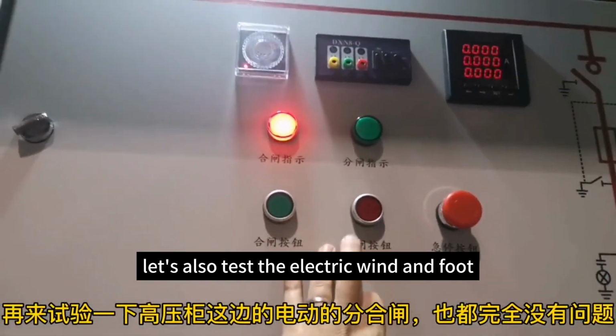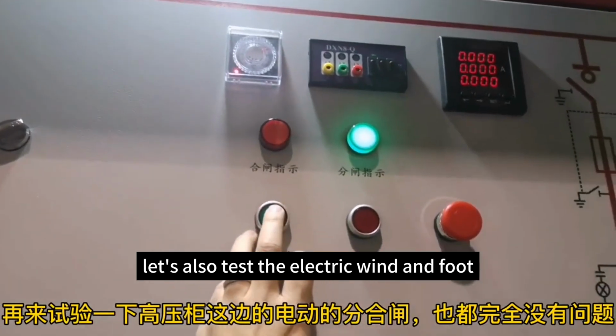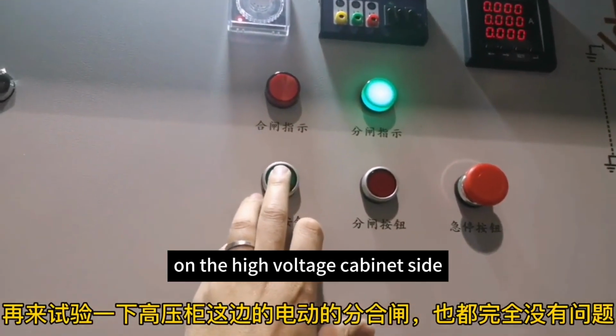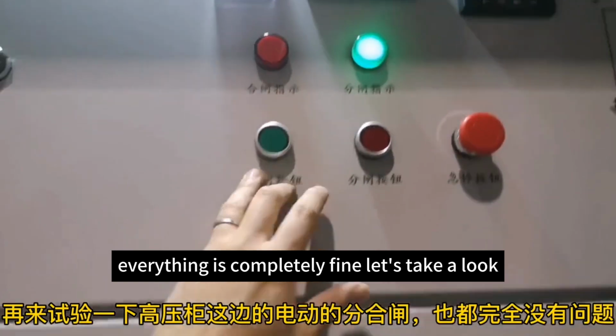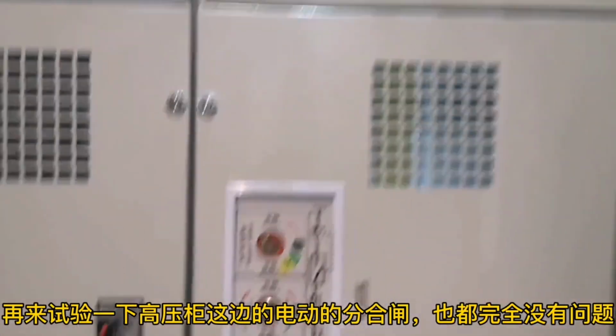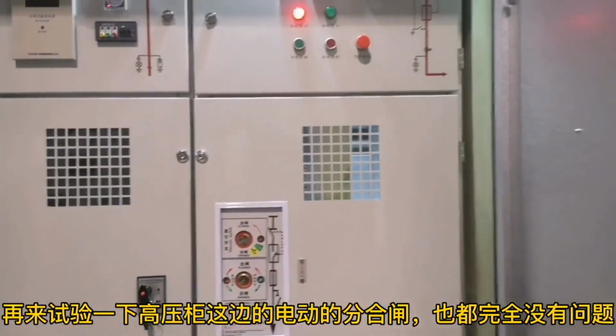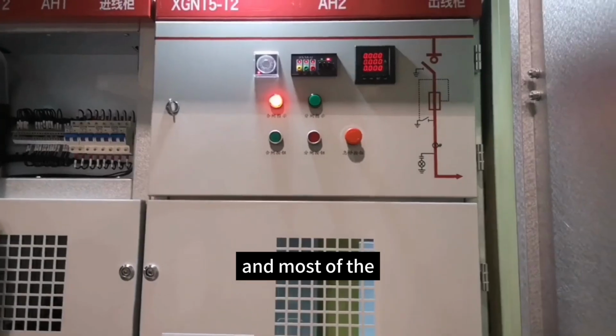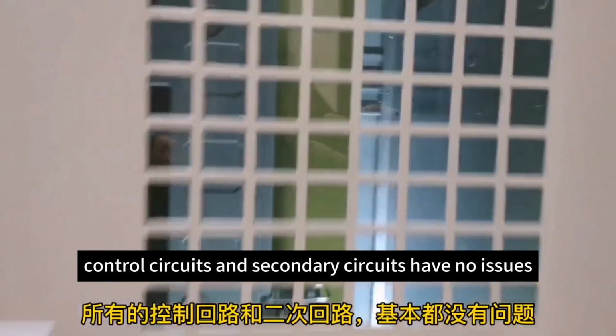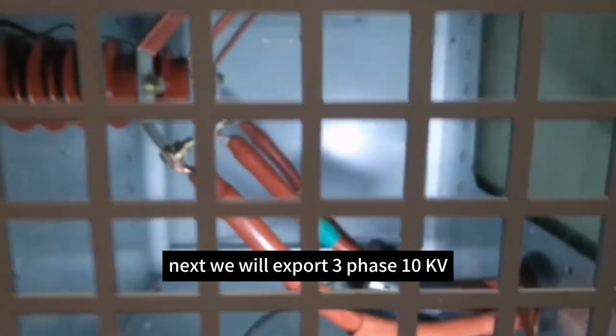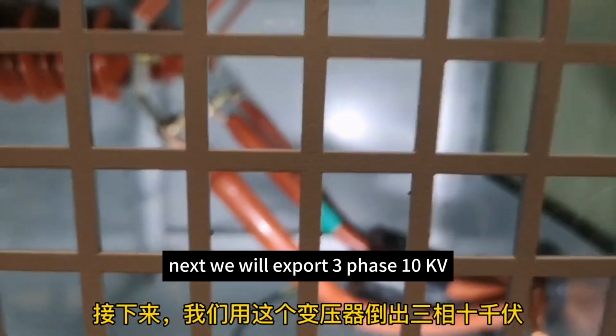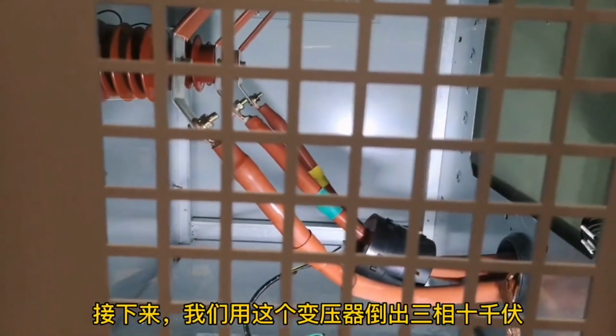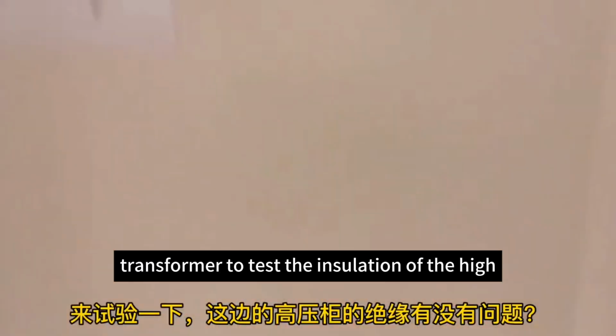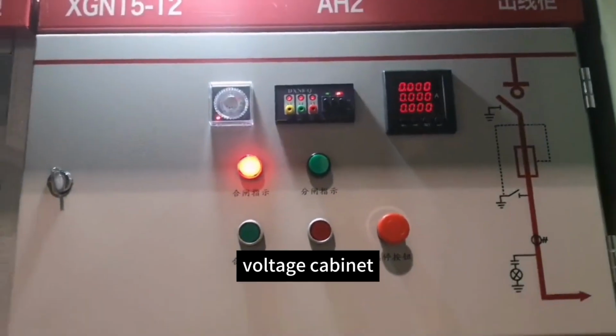Let's also test the electric opening and closing on the high voltage cabinet side. Everything is completely fine. Let's take a look. And most of the control circuits and secondary circuits have no issues. Next, we will output 3-phase 10 kV with this transformer to test the insulation of the high voltage cabinet.